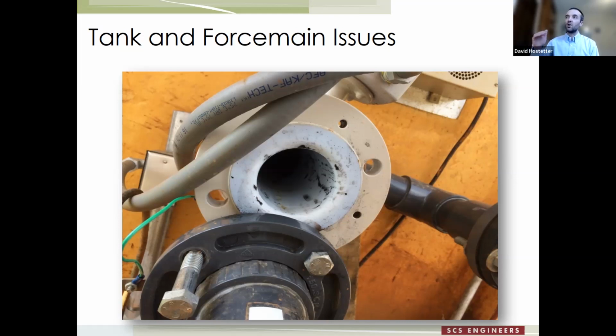There was next to no flow showing on the flow meter, so they quickly figured out that one of the force mains was clogged. Only one of the pumps was running at that point, so they switched which pump was active and basically backfed water through the force main to break the clog loose. That 15 minutes of the RMC system operating prevented the pump station from overtopping and spilling leachate on the ground, another related success story.